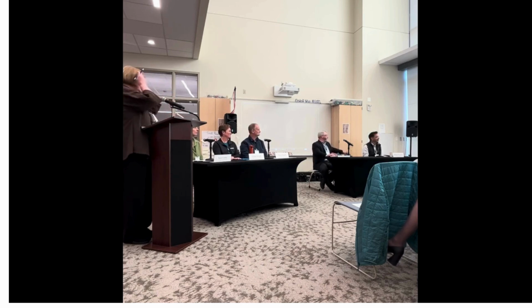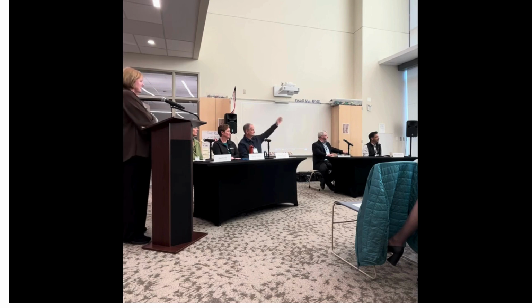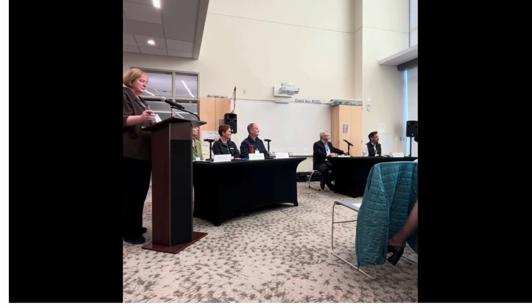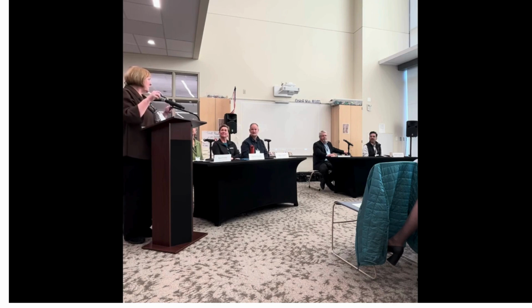We heard about putting wells under the building, but how many on this panel had problems with well fields after they were installed -- not compromised, just something going wrong with the well field? Think about this: if it's under your building and you're still constructing and there's a problem, you're impacting the building, let alone what happens in the future. Not the best of ideas, but you have to make a decision for your community. None of us have well fields under the building for a very good reason. So can you shut off individual wells? Only if they're tied to it -- it would be the whole circuit.